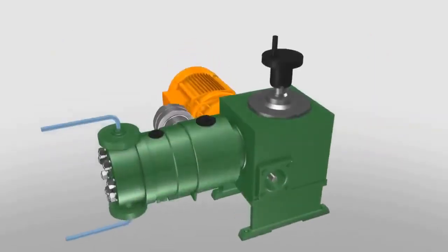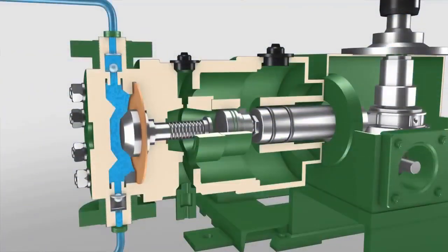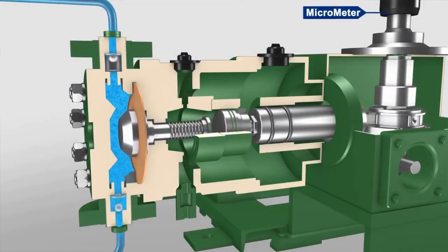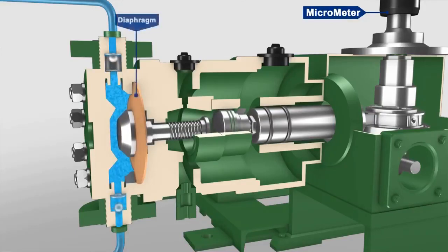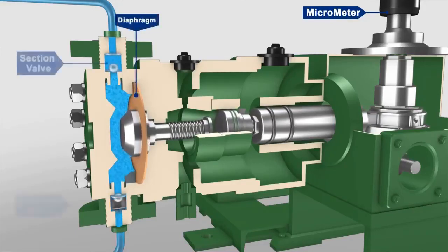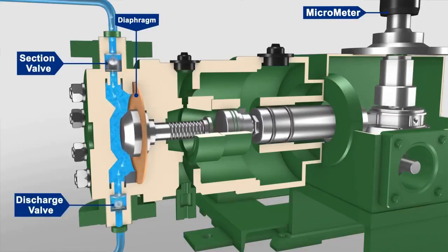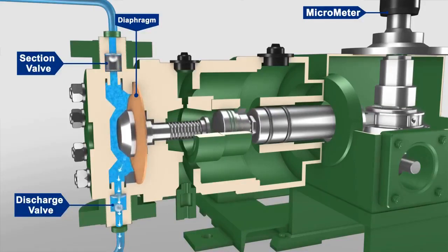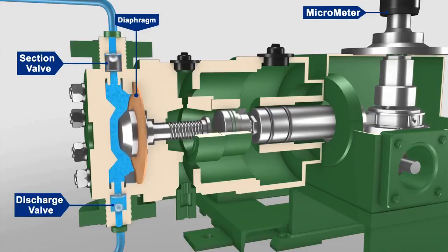Also called a dosing pump, it is a small, positive displacement pump. It is designed to pump a very precise flow rate of a chemical or substance into either a water, steam or gas flow. A dosing pump will deliver this precise flow rate of chemical or other product by drawing a measured amount into a chamber and then injecting this volume of chemical into the pipe or tank being dosed.